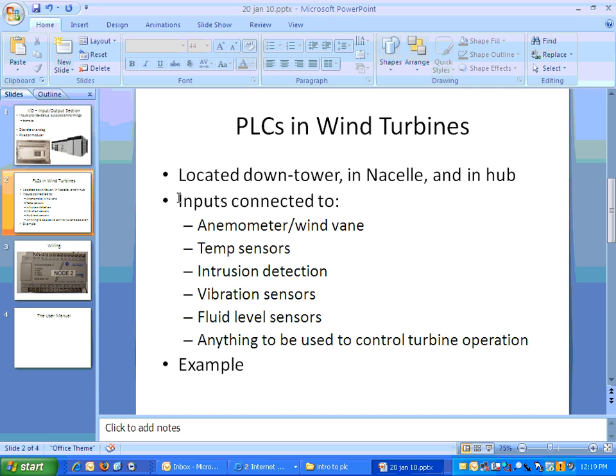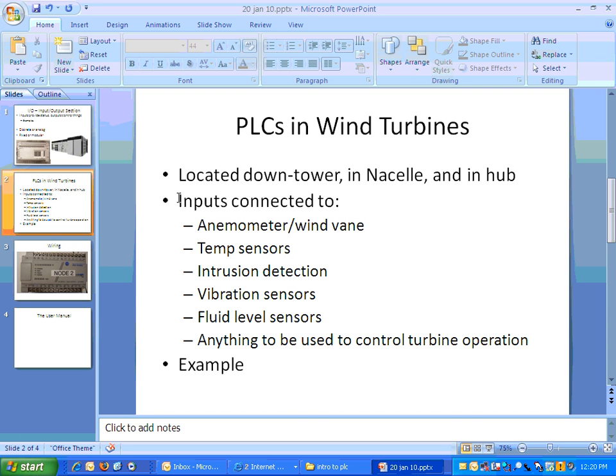Inputs in a wind turbine, the input to the PLC is going to be connected to things like the anemometer. That's the device, usually it's on the rear of the nacelle outside that indicates the wind speed. And the wind vane, which tells you which direction the wind is blowing from. That's pretty important information. In order to have the turbine operate at its peak efficiency, it has to be pointed into the wind and the blades have to be pitched to catch enough wind to generate the electricity needed.